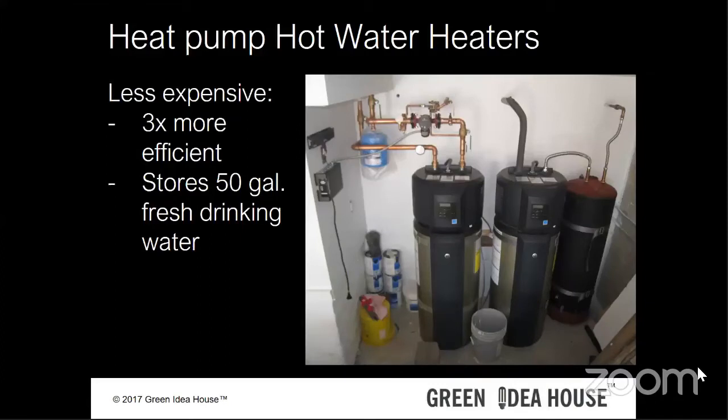It was powered off of that 50-gallon heat pump hot water heater, and it worked just fine. The difficulty was that it was a little undersized, and so the 4,500 watt resistance heaters would pop on, and you could see the profiles that the electricity spiked as a result of that. We recently purchased, because GE was switching their lines and they sold them to Bradford White, a clearance 80-gallon tank for $1,300, and we swapped it out, and so that's what you saw in terms of the reduction of wintertime load.